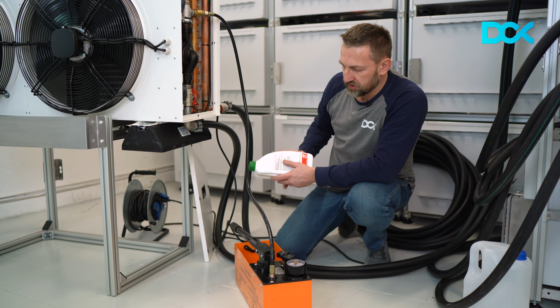So doing like this, and during the pressurization, you will add the anti-corrosion, antibacteria, fungus concentrate, and that's all you need to basically fill the whole system altogether. If there will be some dripping here, some water flowing from here, basically some drips, it's completely fine. It's just a temporary one-way connection. You can make that a little bit more. It doesn't really matter for the operation.